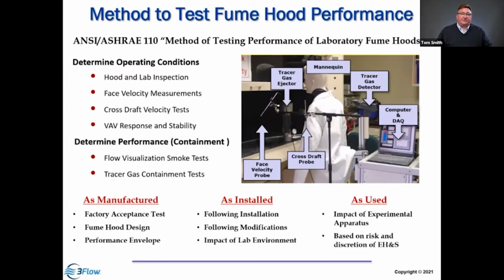As we mentioned previously, there are three methods of specifying the ASHRAE 110. As manufactured, that means that we're testing the hood by itself. How does the hood perform as a function of its design, right? And then we'd like to know, where is its failure point? How low can we go on the flow before it begins to fail?